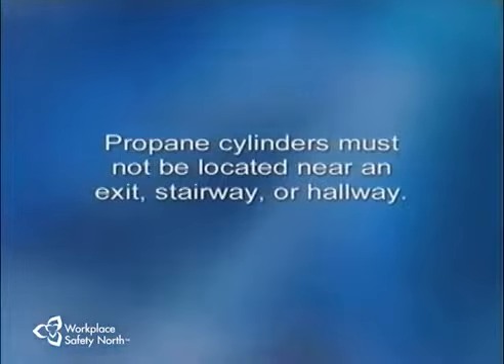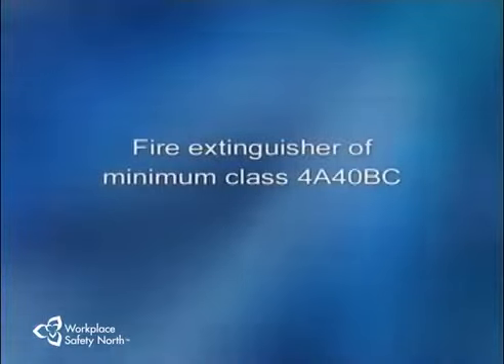A propane cylinder used inside a building must not be located near an exit, a stairway, a hallway where there is a lot of traffic, or an area used or intended for the safe evacuation of people. A fire extinguisher of minimum class 4A 40BC must be kept nearby.